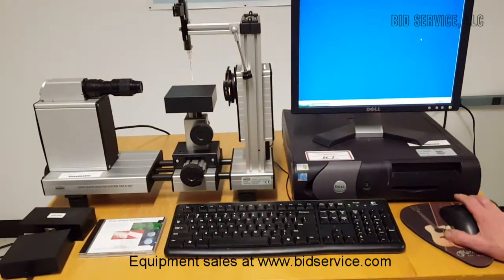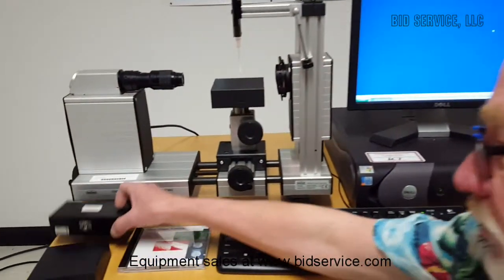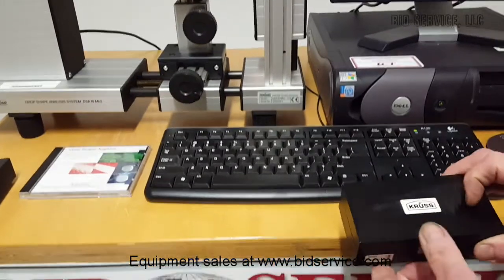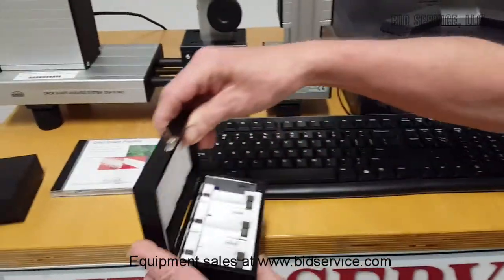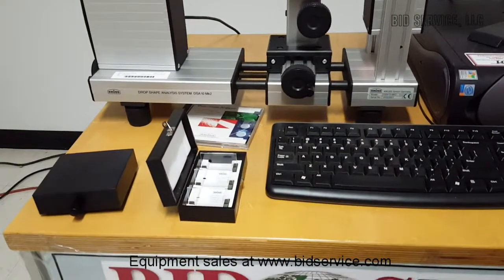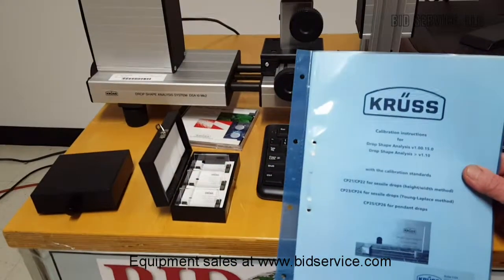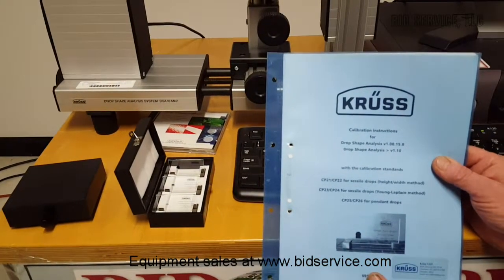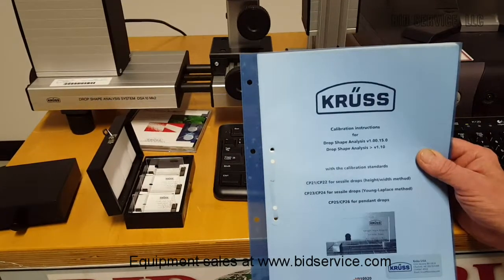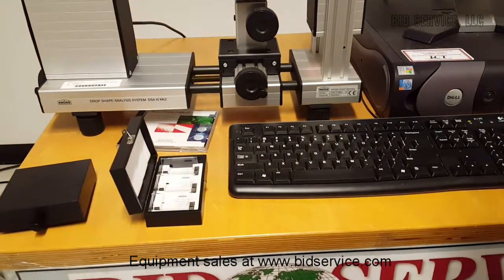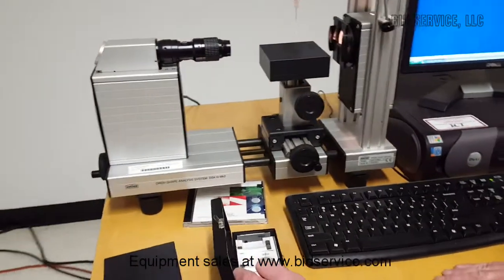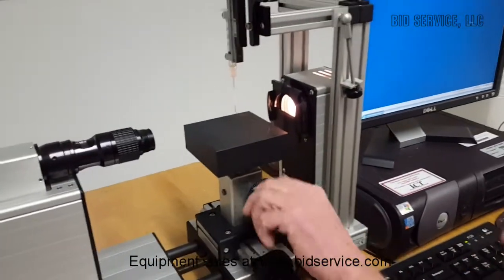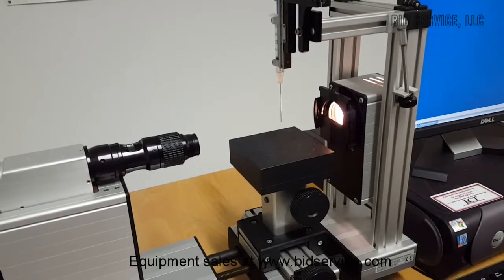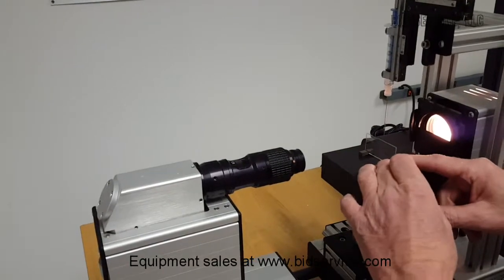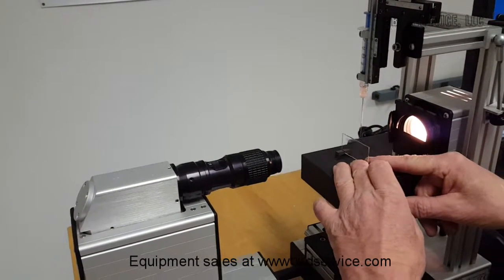Now, we're going to start off by demonstrating it by using these standards that come with the instrument. These are very, very handy. They're actually calibration standards. They also come with a very detailed instruction on how to calibrate the equipment, especially to your particular application. So we're going to start off, we'll use this one first. Now, we'll lower our stage, and I have a rough place that I put these, and we'll leave that right there for now.